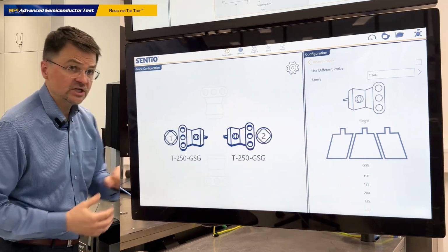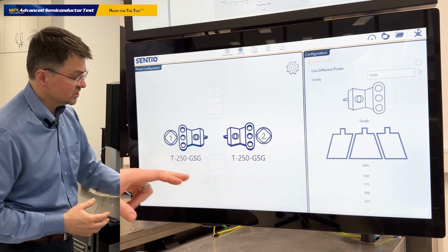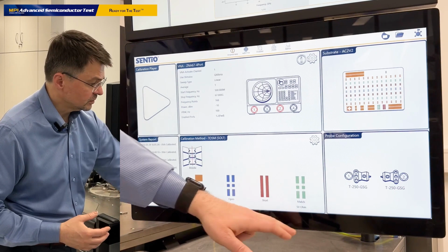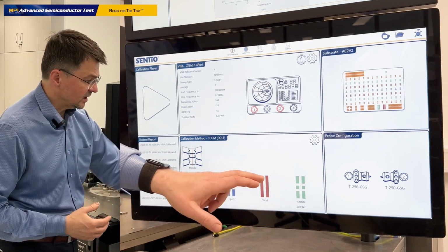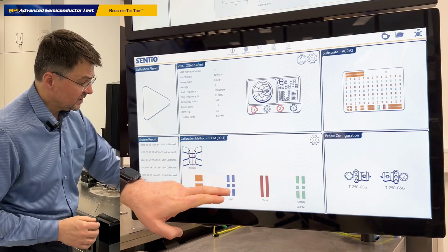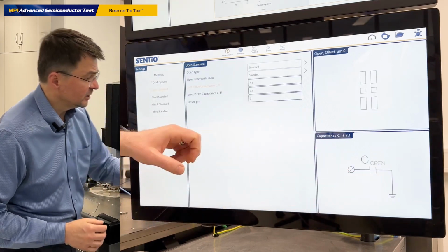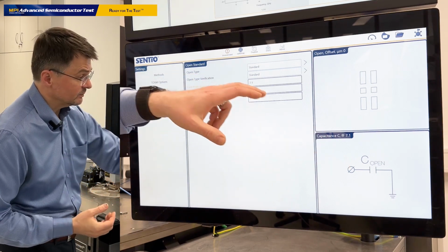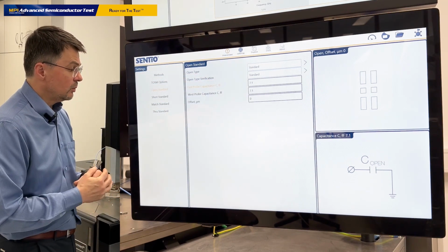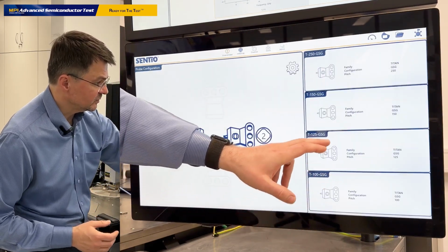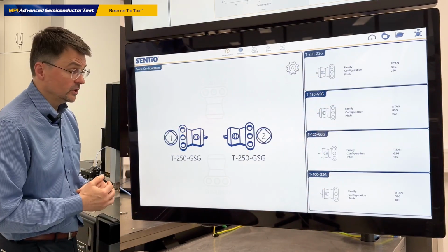And by just changing the pitch of the probe and changing the probe configuration from here, we also change, as we just discussed, the equivalent models of our open, short, and load standard. Let me give an example. What is the open capacitance of the probe measured by a 250 micron ground-signal-ground probe? This is 7.1 femtofarad.